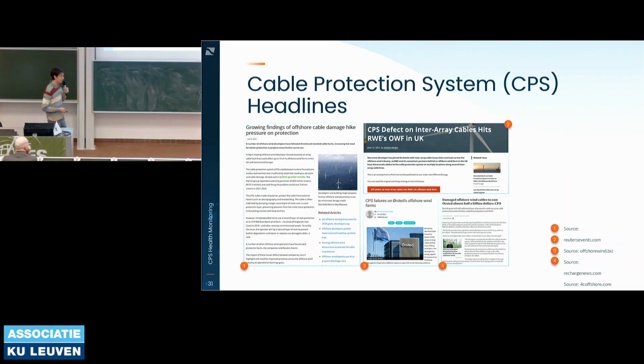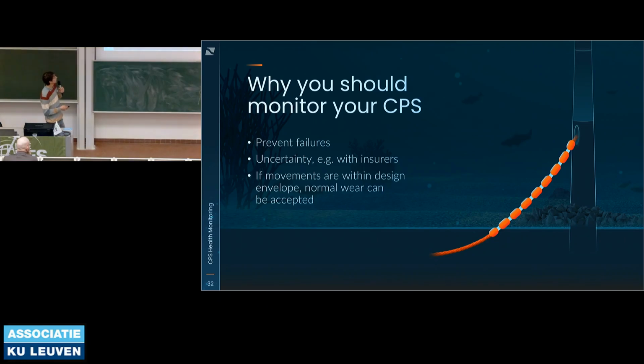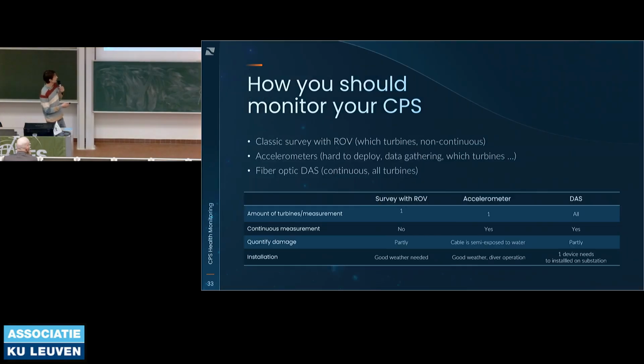CPS systems have been introduced by Dries. A few years ago, Ørsted realized a cable fault was due to possibly faulty design in the CPSs, they were not stabilized, so they didn't have the stabilization layer on it. They had a warranty provision and expected, I believe it was 3 billion, that they foresaw to mitigate all of these problems in their wind farms. It didn't end up that bad, but that raised quite a bit of issues. So one of the things we're doing is CPS monitoring.